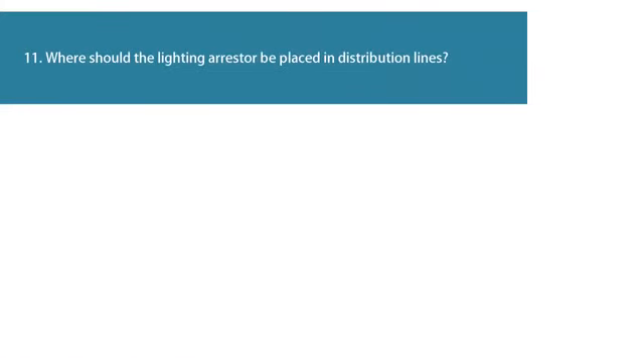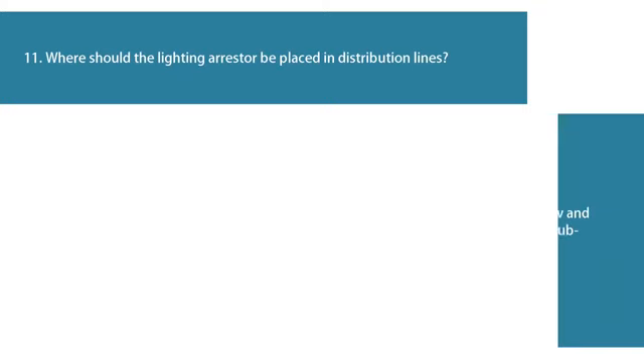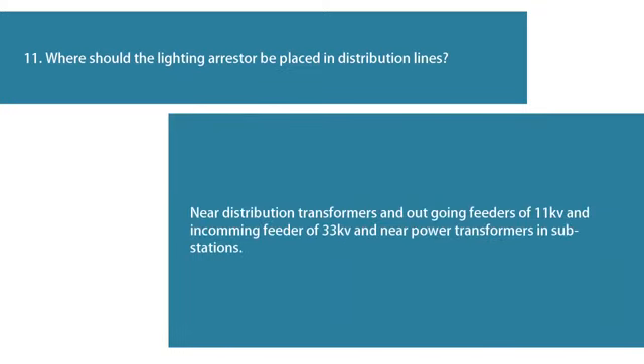Question 11: Where should the lightning arrestor be placed in distribution lines? Near distribution transformers and outgoing feeders of 11kV, incoming feeders of 33kV, and near power transformers in substations.